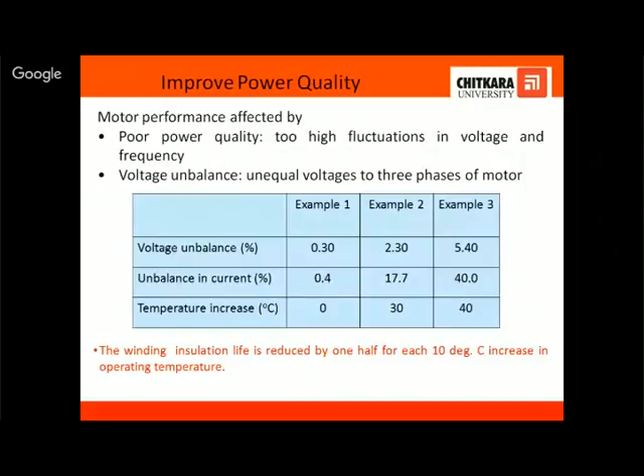Now coming to power quality. Poor power quality means there are fluctuations in voltage and frequency. Voltage unbalance means all three phases of the motor are not equally loaded, so there are unequal voltages in the three phases of the motor. The voltage unbalance may occur because, at the transformer from where the supply is coming, all three phases are not equally loaded. That is just a small example. If there is a voltage unbalance of 0.3%, then the current unbalance will be 0.4% and there won't be a temperature rise. But if there is a voltage unbalance of 2.3%, then the current unbalance will be 17.7% and the temperature increase will be 30 degrees Celsius.